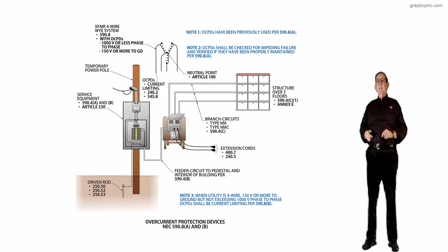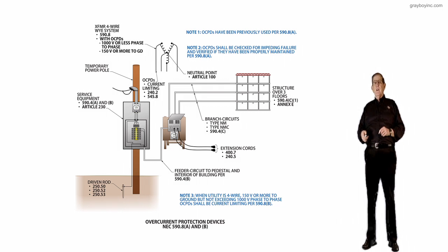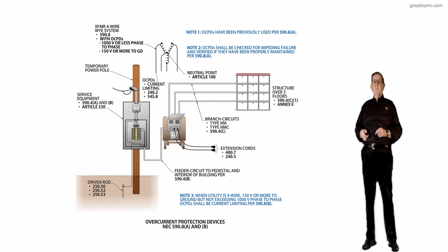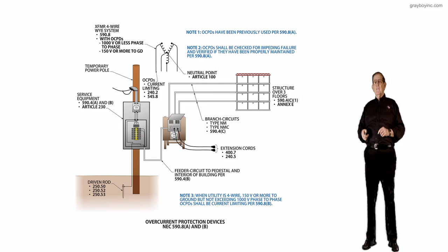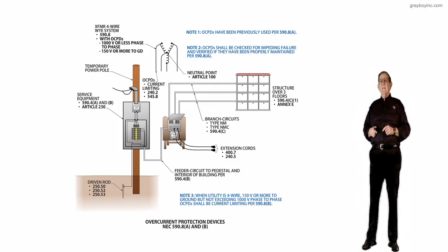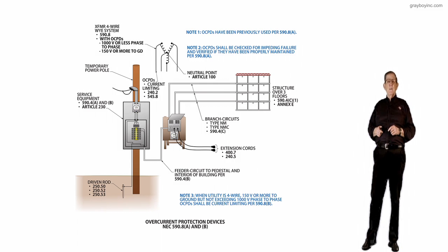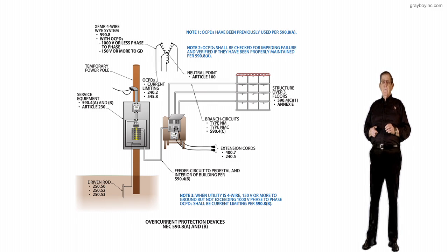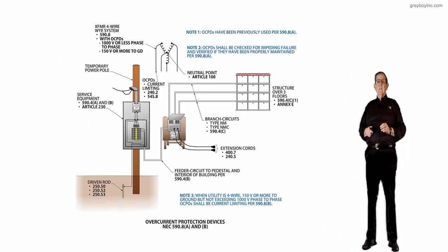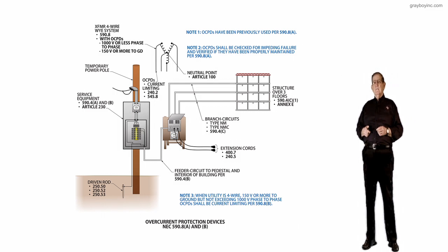Now, picking up the final note 3 at the very bottom, right above the caption, overcurrent protection devices. Note 3 says, when a utility is 4-wire, 150 volts or more to ground, but not exceeding 1,000 volts phase to phase, overcurrent devices shall be current limiting as required in 590.8(B). And of course, current limiting for overcurrent devices can be found in 240.2 of the NEC. It defines what current limiting is and what we have to do to provide current limiting to certain types of equipment. In this case, equipment used to supply items for construction purposes in 590.8(A) and (B).